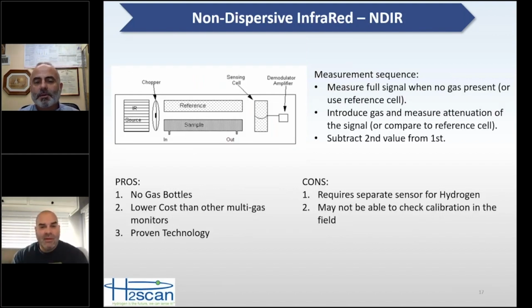Okay, so NDIR, non-dispersive infrared, or some people just say infrared. There's some different variations. This is actually the technology I know the least about, and so I hope I don't mislead anybody or say something that's not correct. But in general, my understanding is that for people using this technology, there are no gas bottles required. The way the technology works, by the way, is you extract the gas from the oil. There is a measurement done before you introduce the gas. So the measurement is done using a reference cell. You introduce your gas into the IR cell, and then you subtract the second value from the first to come up with your result. So again, I'm not super familiar with this technology, so I do look forward to learning more about it in the future.